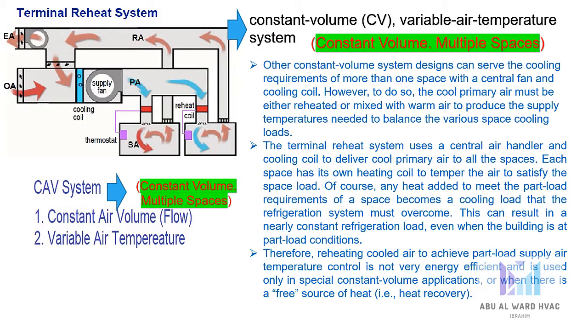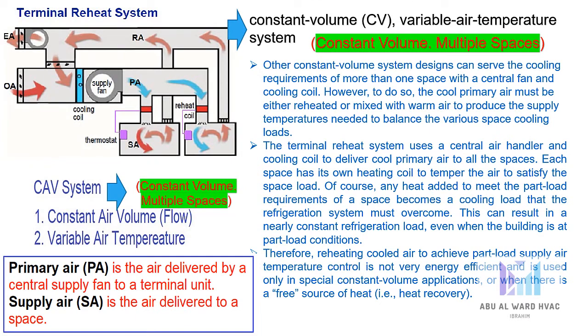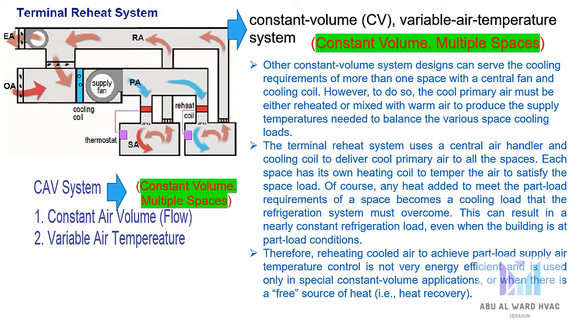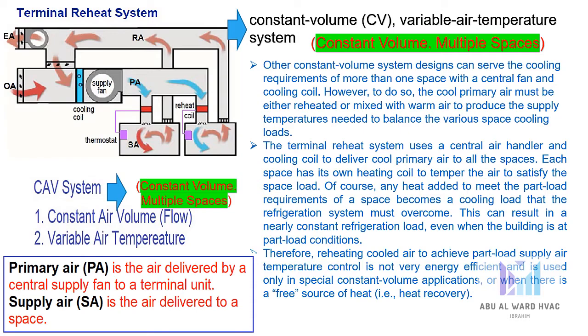Any heat added to meet the part load requirements of a space becomes a cooling load that the refrigeration system must overcome, resulting in a nearly constant refrigeration load even when the building is at part load conditions. Therefore, reheating cooled air is not very energy efficient and is used only in special constant volume applications or when there is a free source of heat, such as heat recovery. In this system, we have primary air (PA), which is the air delivered by a central supply fan to a terminal unit, and supply air, which is the air delivered to the space — making it a two-stage process compared to a single-stage normal CAV.